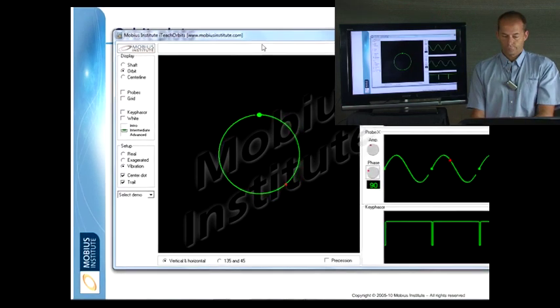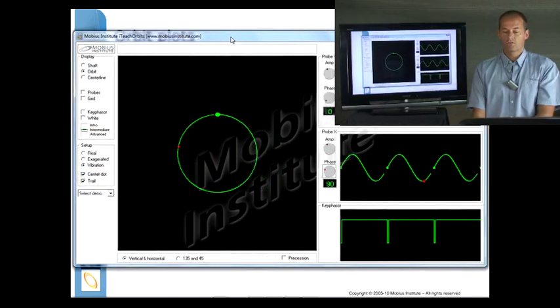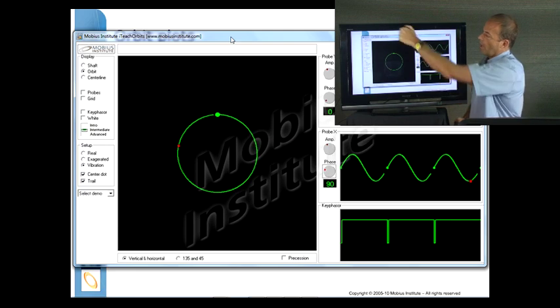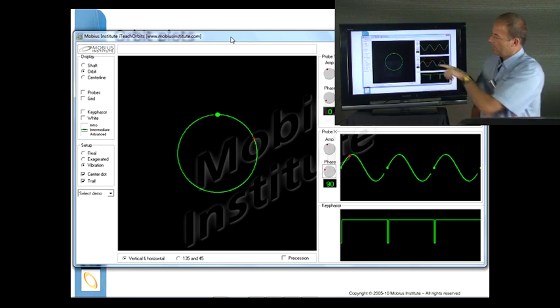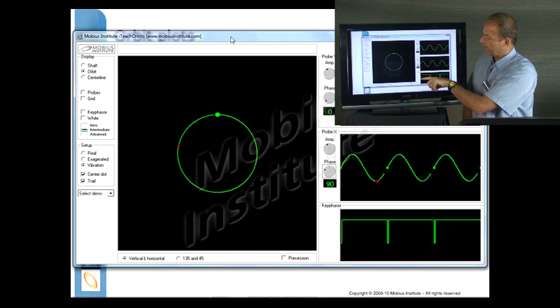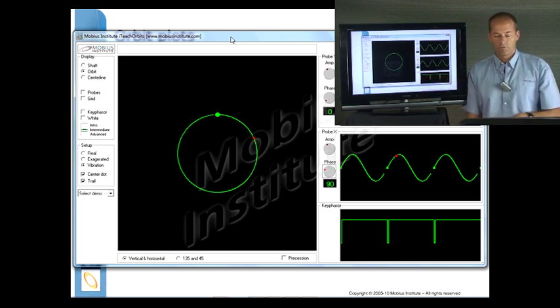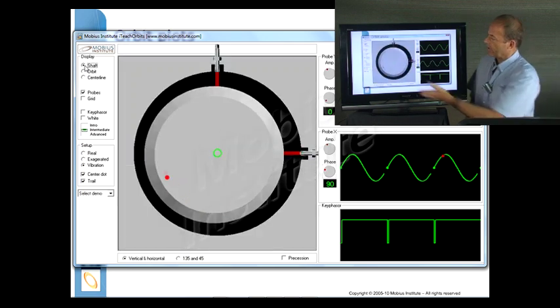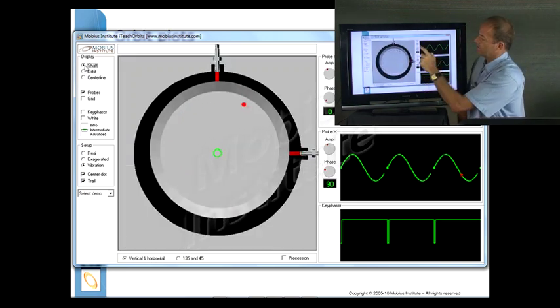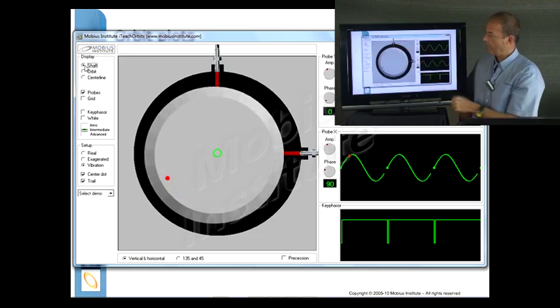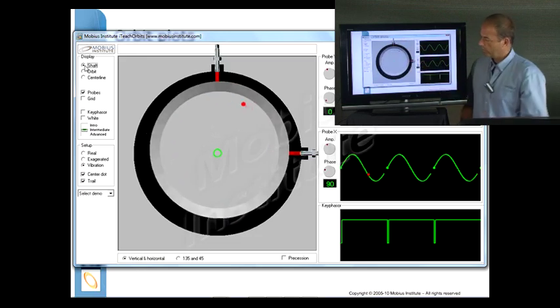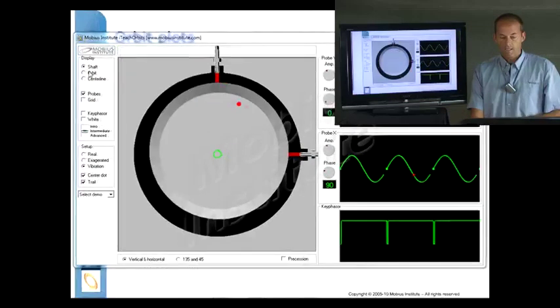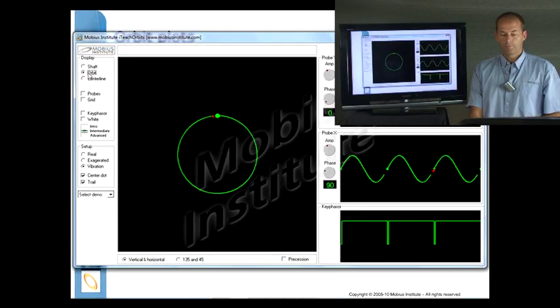Now what I can do is just show you those voltage signals. So there is the voltage from my Y probe, which was up on top. The voltage from my X probe. And I have also got my key phase, a sort of once per revolution signal. When I plot those against each other, I end up with an orbit plot.